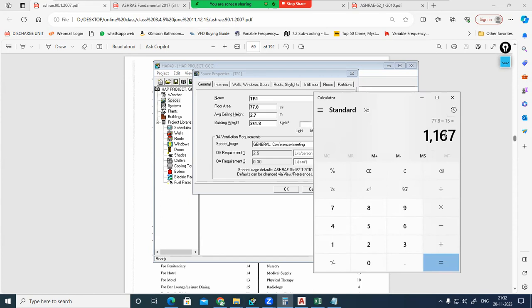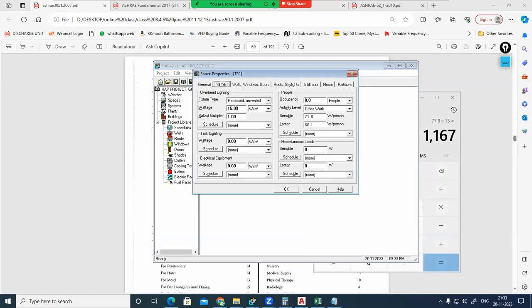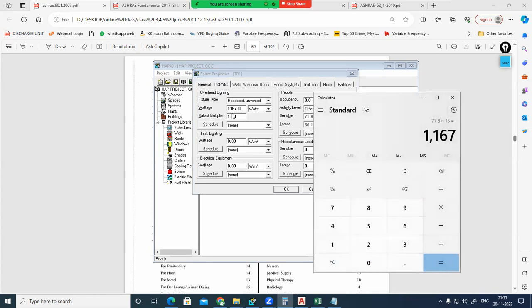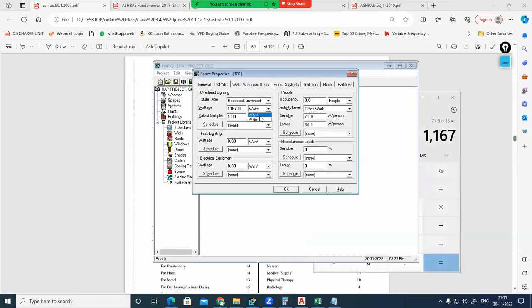1 meter square, 15 watts. Like that, 77.8 meter square, 77.8 into 15. If you have doubt, after providing the LPD value, change the unit from watt per meter square to watts. How much is it? 1167. So the watt calculation we have performed here, the software will also do in the background. Now, understood how to calculate the lighting load? Floor area into watt per meter square, you can find it.